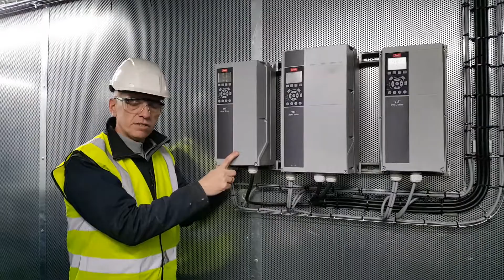We have another 2 VSDs, giving very low parasitic losses in these engines. This is for the heat dump on the roof. We've roughly 5 kilowatts of fans on the sandwich cooler, so a variable speed drive for that, and we also have a variable speed drive for the jacket water pump.